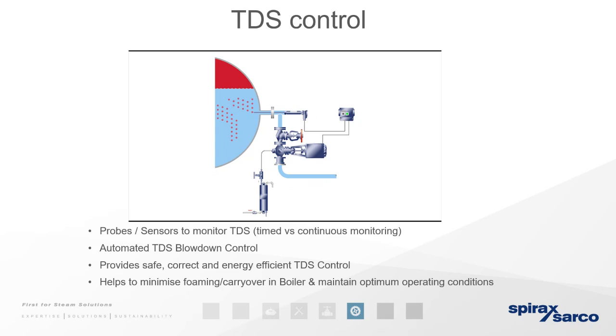Yeah, the only thing I can think of is, like I stated, it'd have to be an unequal pressure difference across the tube of the Mobrey. So the only way I can think that can happen is by a blockage on one of the ports. But again, if it's blown down properly, it shouldn't happen. I think you've got the sequencing valves that should be able to make sure that you're blowing down those properly. Again, it'd be more interesting to hear more about that so that we can properly diagnose for you. It shouldn't be, they're pretty robust, to be honest, so they don't tend to fail often, but like anything, they can fail. So yeah, please get in touch afterwards.